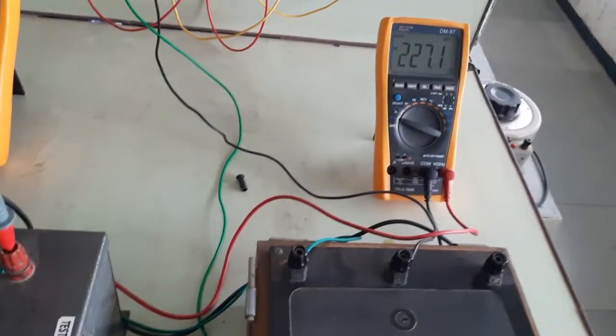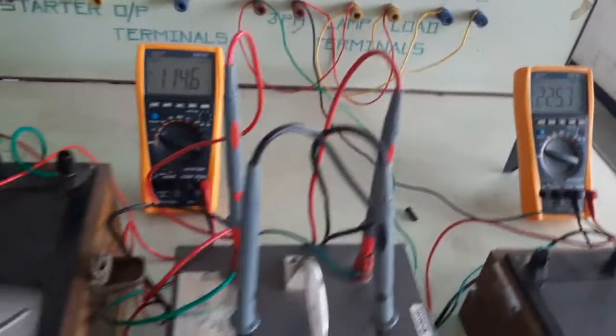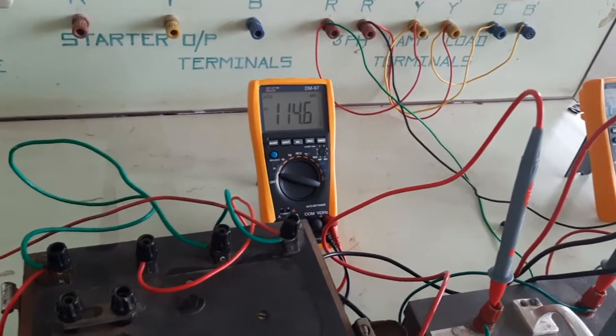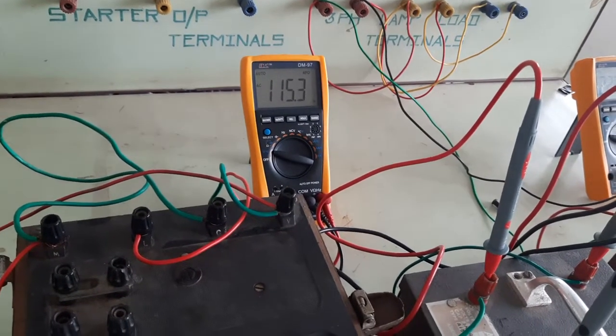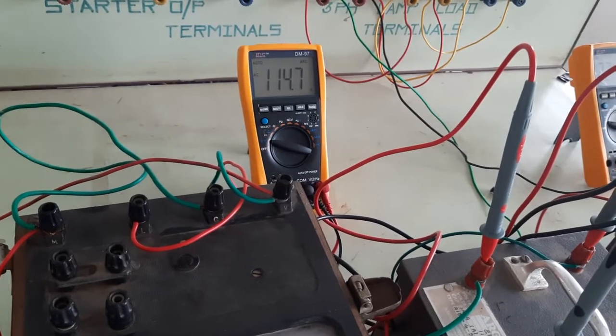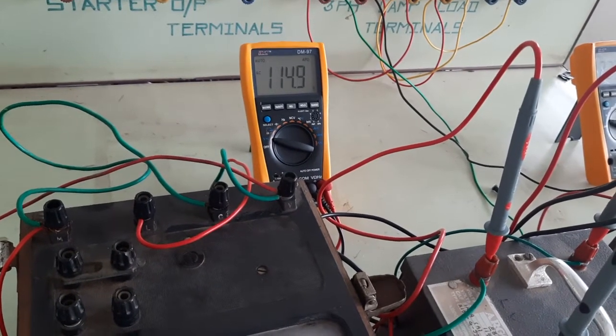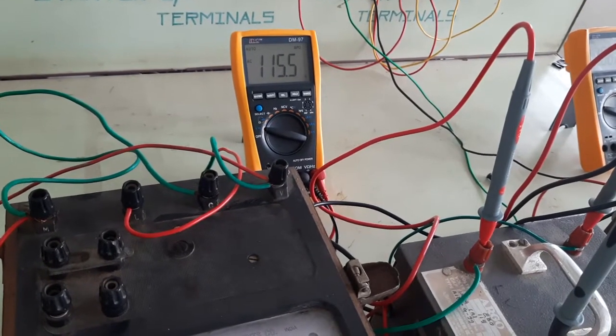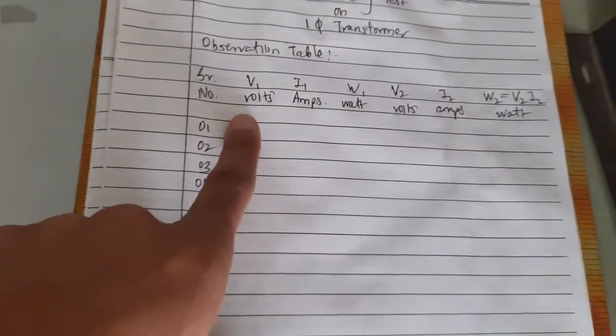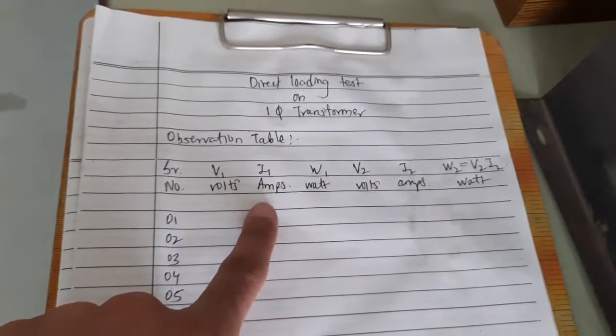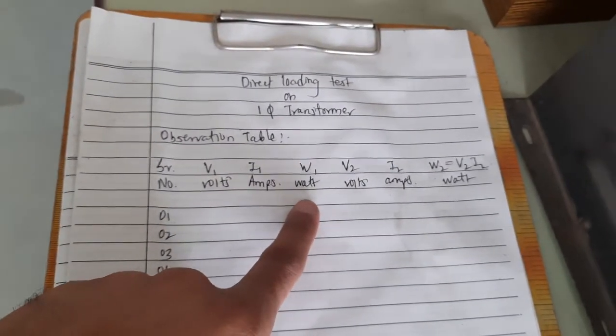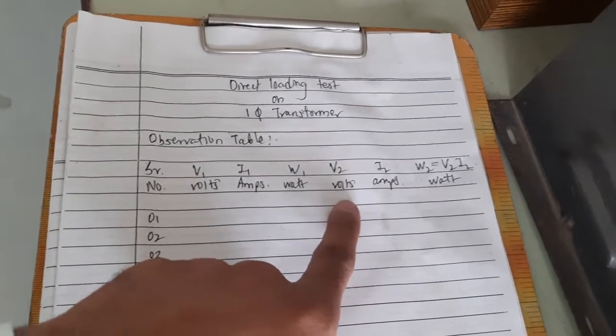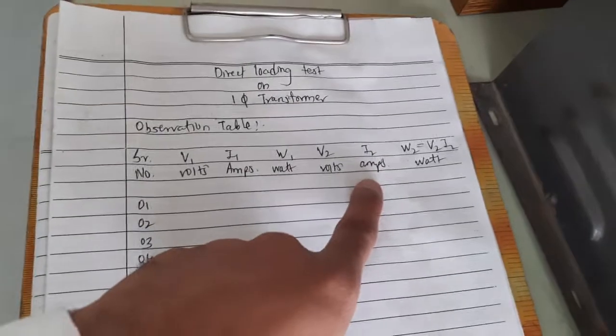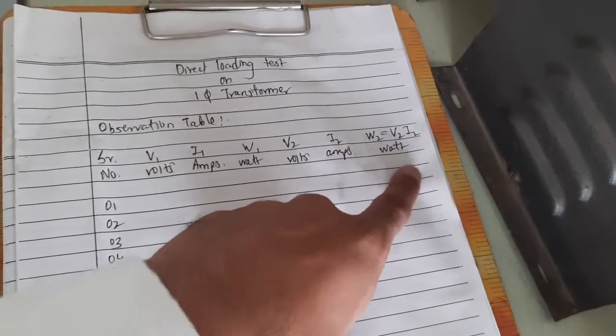The multimeter will show the voltage reading directly. So let us adjust it again. Okay, the first reading will be the no load reading. Now do not change the voltage, it will be constant throughout. So we need to take the reading of the primary voltage, which is 115 volt, then the current, which will be around 0 ampere, wattage around 10 watt, V2 which is around 230 volt, then the secondary current, which is almost 0 as we can see here. W2 will be calculated as V2 into I2, so it will be 0.